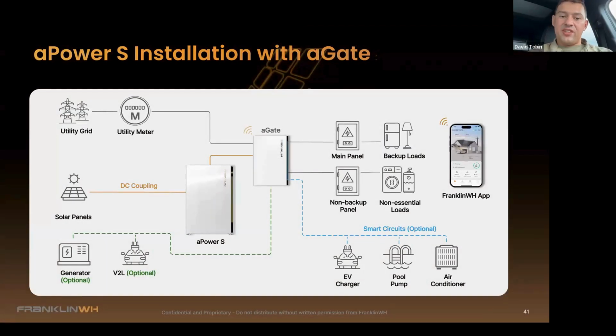Using the aGates and the aPower S, you can do whole home backup or partial home backup. We have a split CT kit, and I've seen a lot of partial home backups on the west coast of Canada, especially near Vancouver and Vancouver Island. They use our split CT kits to monitor the loads left upstream of the aGate, with a protected loads panel downstream. Sometimes the homeowner just wants to make sure certain loads don't get backed up, so only the loads they really want are using the power, and it was more cost effective for them to leave those loads upstream rather than get smart circuits.